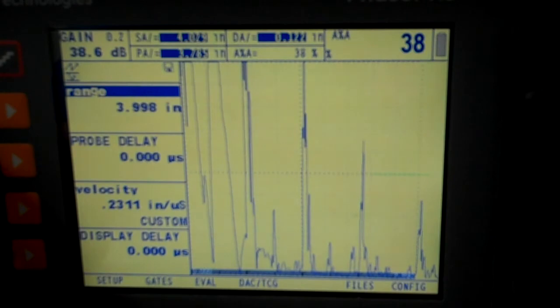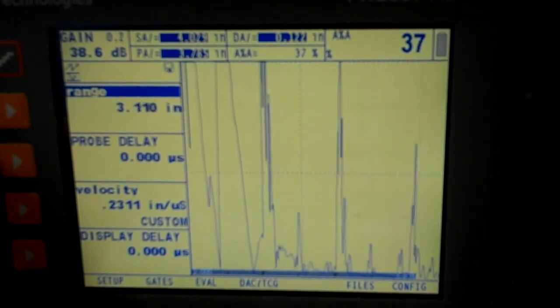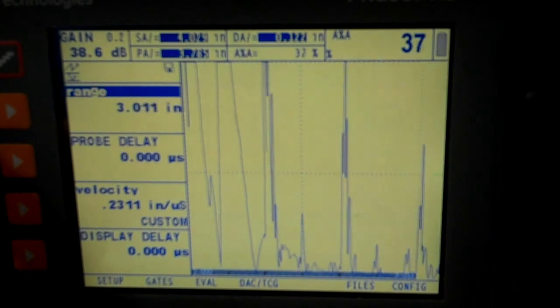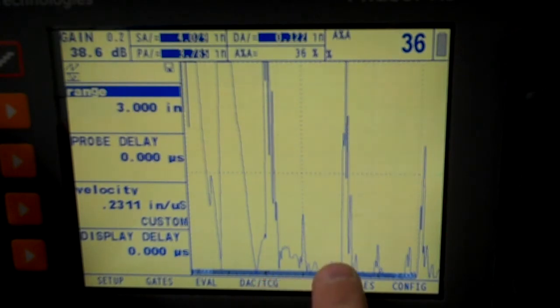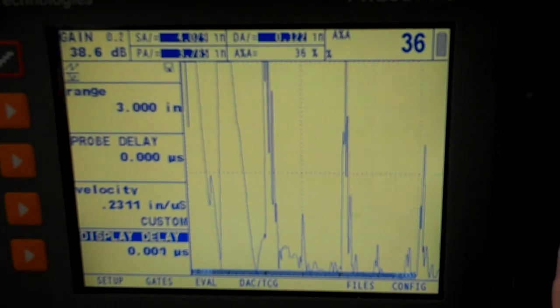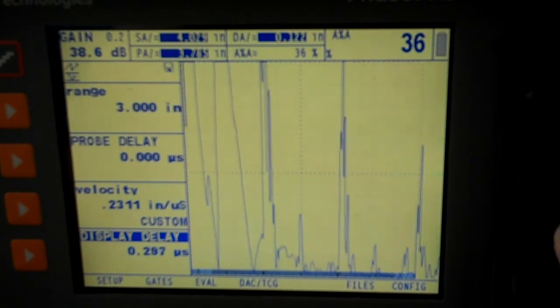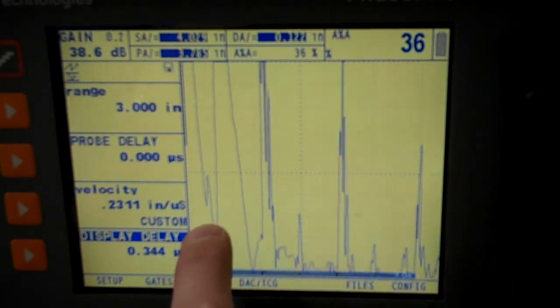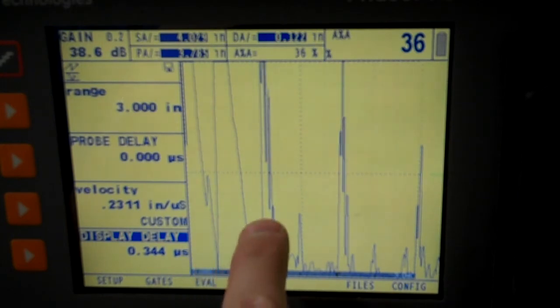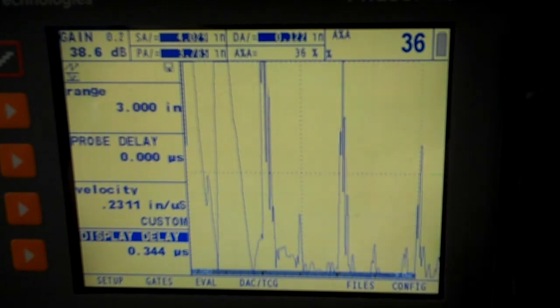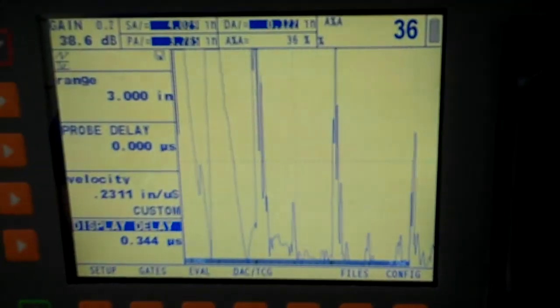So we go to a 3-inch range, start bringing it down. Now we should see signals at 33, 66, and 99. Alright, so we're close. We're a little past 100. There's 62, 64, 66, so we're a little off. So let's take our delay and push these over. 33, 66, and 99. Okay, so here's 10, 20, 30, 33, 66, 99. Alright, and that's what we want to know. So there's our 1-inch block, and there's our screen representation of our 3-inch range.